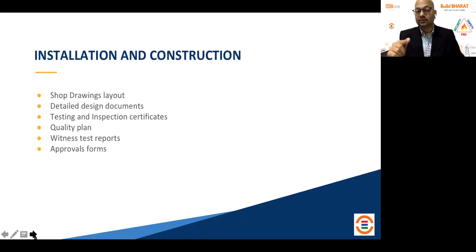The purchase manager will only follow what has been assigned to him. If your system itself is weak and isn't giving him enough information to procure the right equipment, there are chances he'll make a mistake and just go by commercial logic - the lowest bidder gets the order. So you end up with 300 extinguishers in your facility without a certificate. Then when a real case comes and you want to operate the extinguisher, there's no pressure, there's no gas.